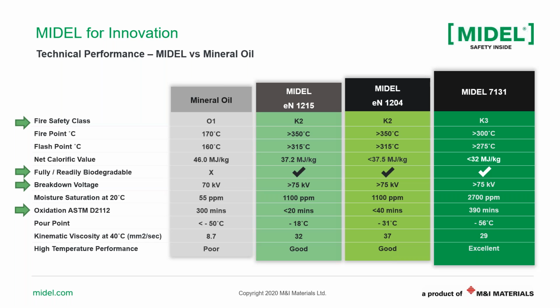On the first column, you see certain parameters that are of interest to compare between mineral oil and esters. The first one, of course, is the fire safety. Esters are mainly used in transformers because they offer elevated fire safety. And how we classify that is using the fire point and the net calorific value. So let's first talk about mineral oil. Mineral oil is known as an O1 class liquid. And O meaning its fire point is lower than 300 degrees. So you see in the table a typical fire point value for mineral oil is 170 degrees.